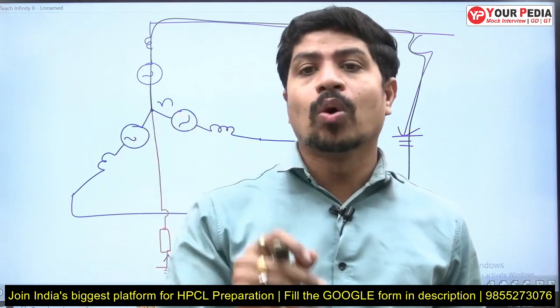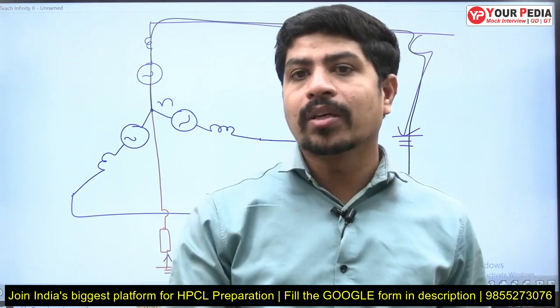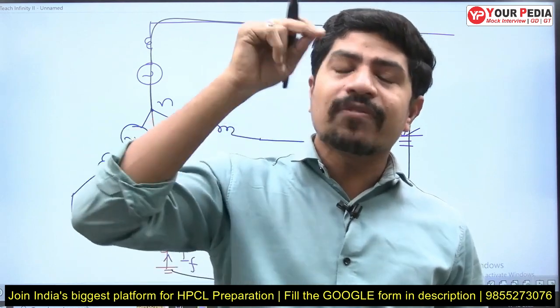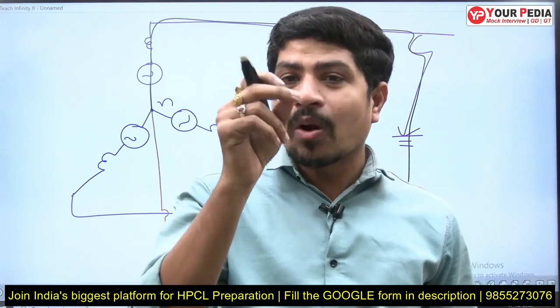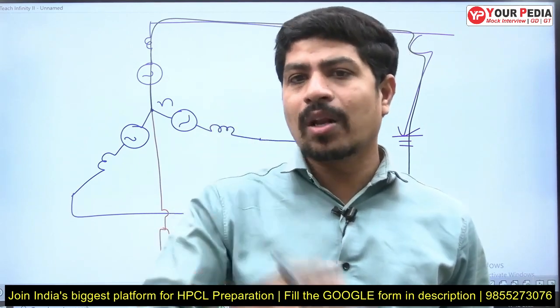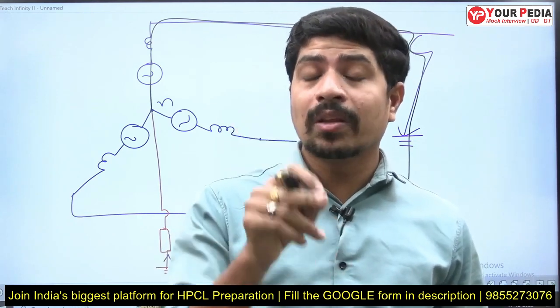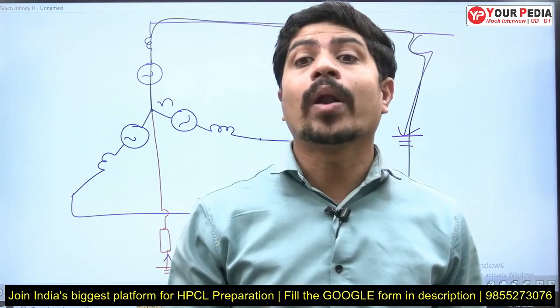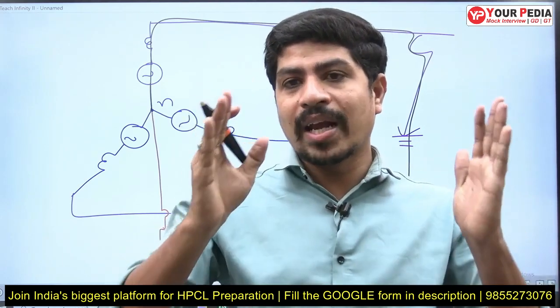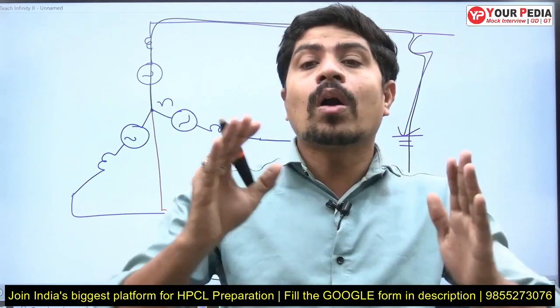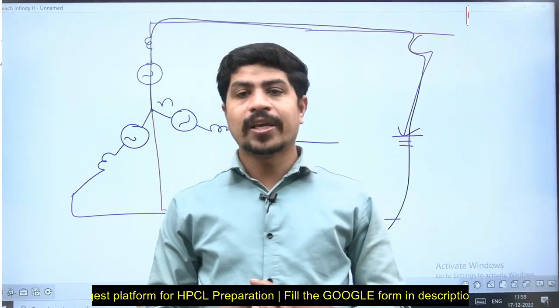Neutral grounding also reduces the imbalance effect. Every three-phase system equipment neutral must be grounded if neutral is available. If it is a delta connection, neutral itself is not available, so there is no question of neutral grounding. But if it is a star connection, then definitely the neutral must be grounded. So this is the solid difference between grounding and earthing — please do not treat those two as the same. Both are very much different. Thank you.